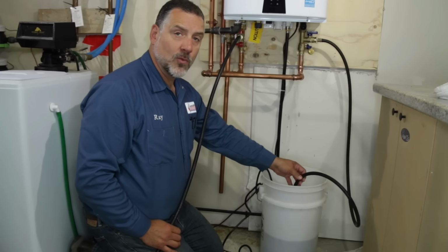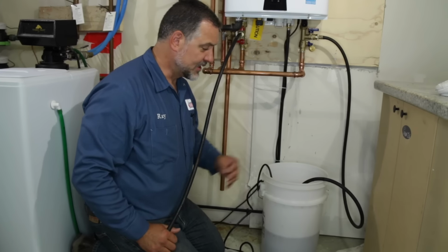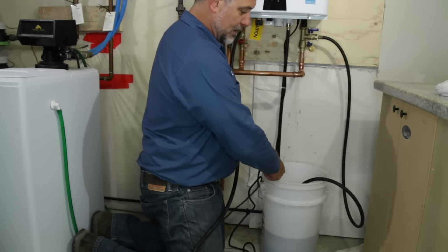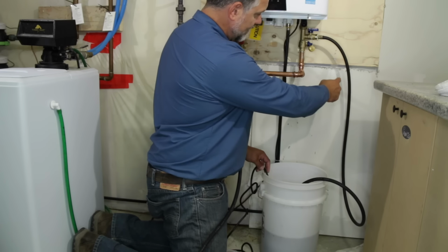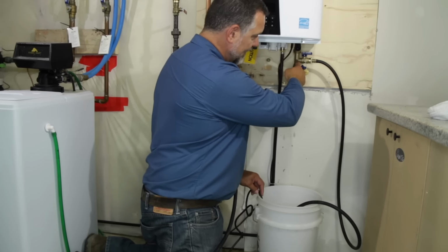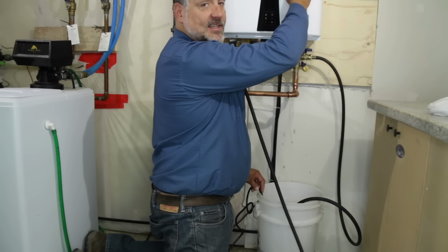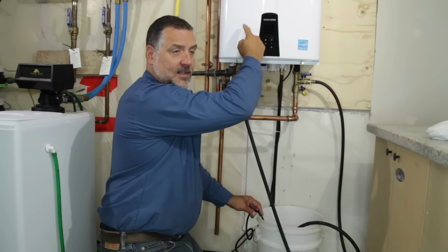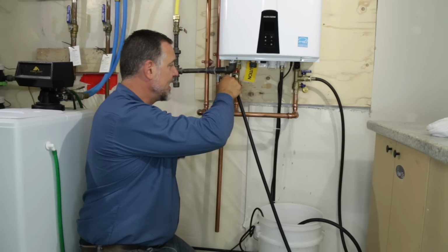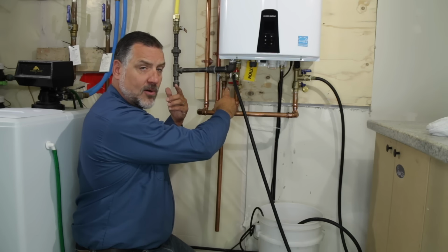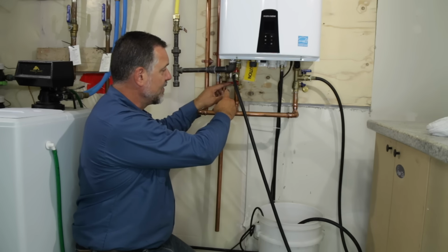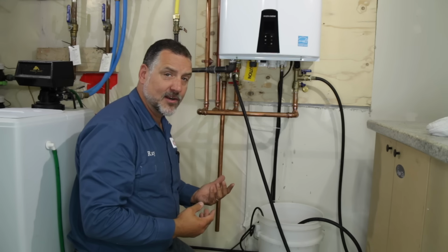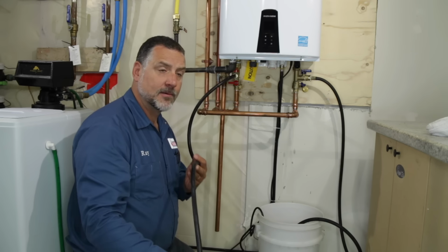We have the cold water inlet hose attached to the sump pump, which is going to pump water through this hose into the cold water inlet. It's going to go up into the heat exchanger and come back down through the hot, as if it were normally going to go through the house, except we have it shut off here. So it comes out this outlet right back into the bucket, and we're going to transfer this white vinegar through the system for about half an hour.